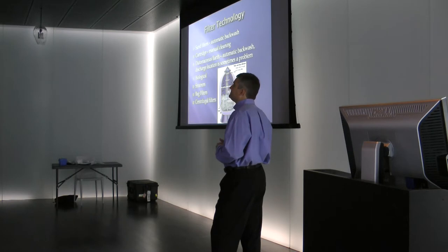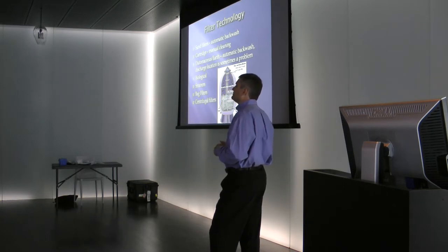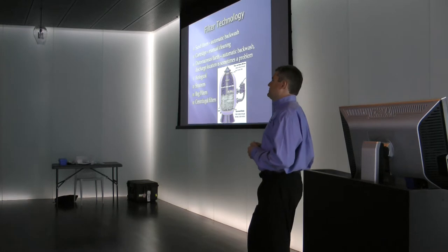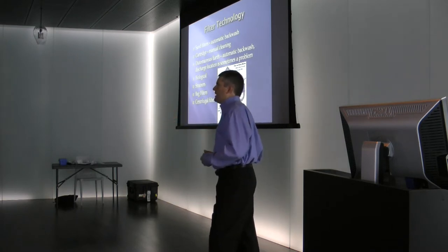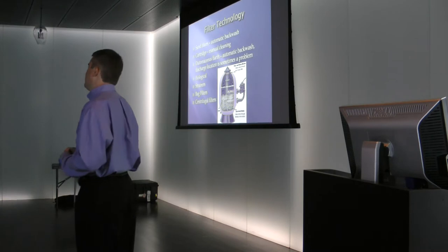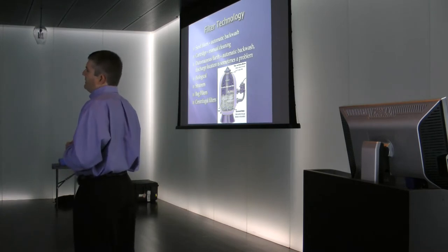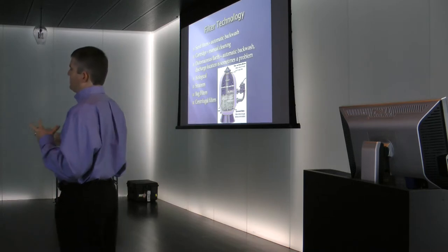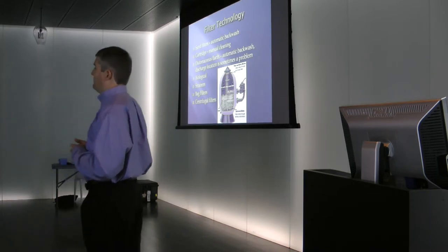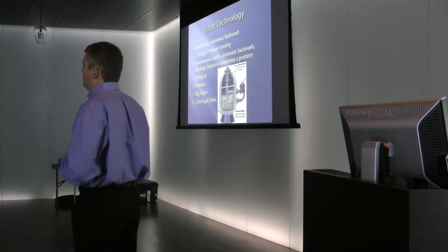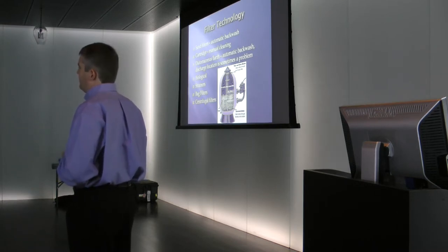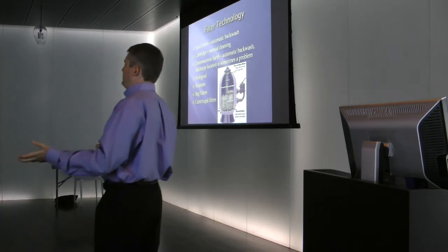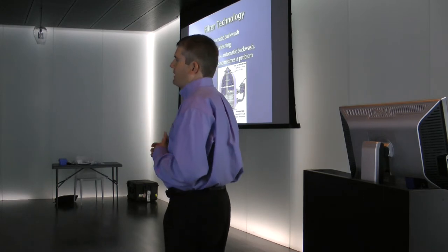You were talking about skimmers and being able to skim off leaves. Is that system going to even deal with that large floating debris, or is it going to get macerated in the process? It will. If you have leaves, though, I would say that you want a pump that's got a strainer in front of it, either an integral strainer or a separate strainer in front of the pump, to catch some of the bigger debris, because you don't really want that going through the impeller of the pump anyway. You could do an open impeller pump, and there are certainly pumps that handle up to like 2-inch diameter solids fairly easily, but I would rather not send that stuff into the filter. If I could catch it ahead of time with a strainer, I would do that. But I think the story was that the goose stuff was just too slimy. It'll go through a strainer.